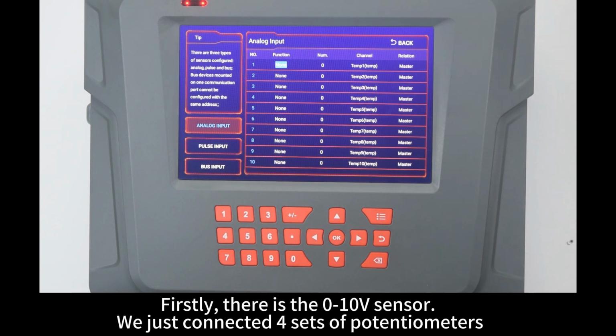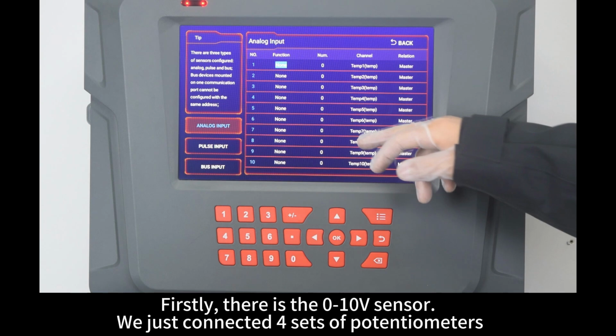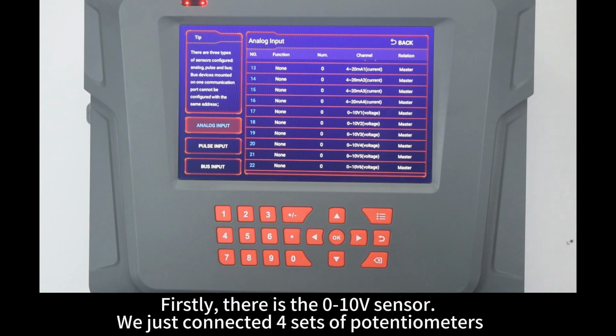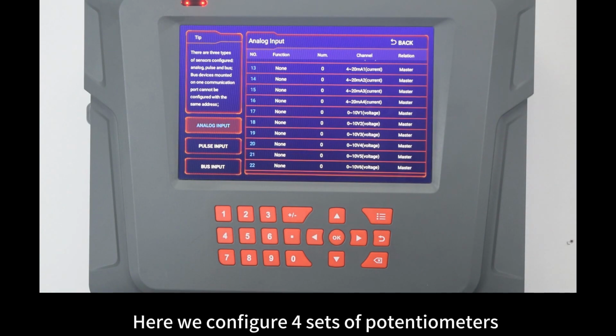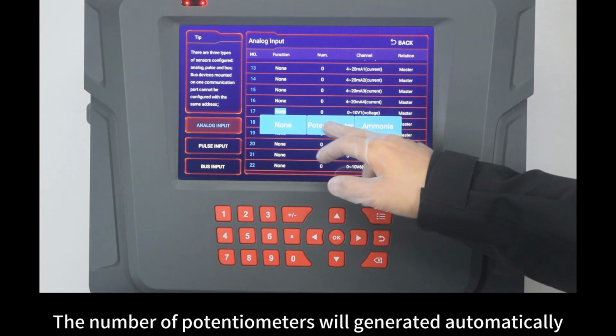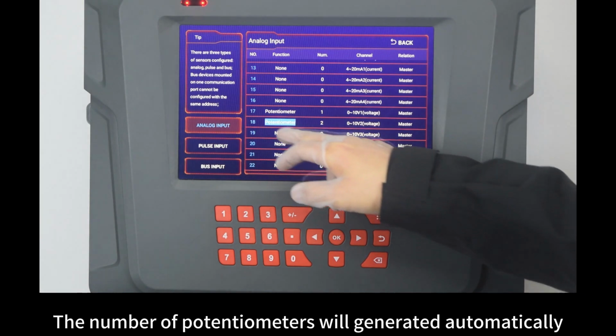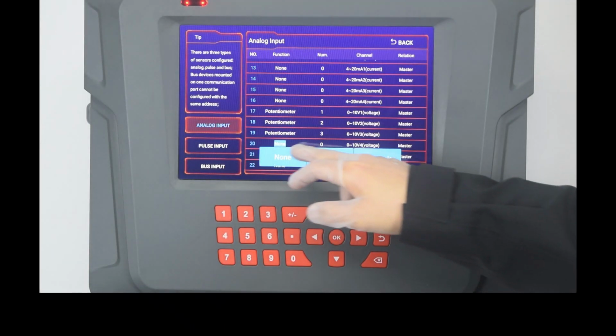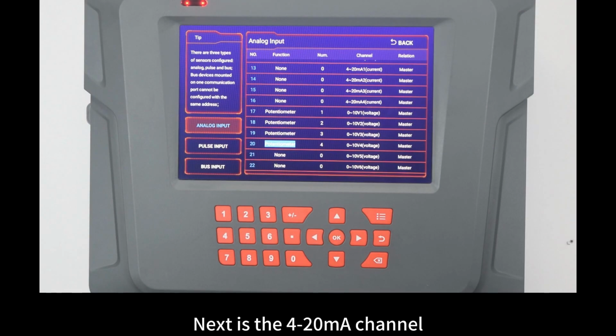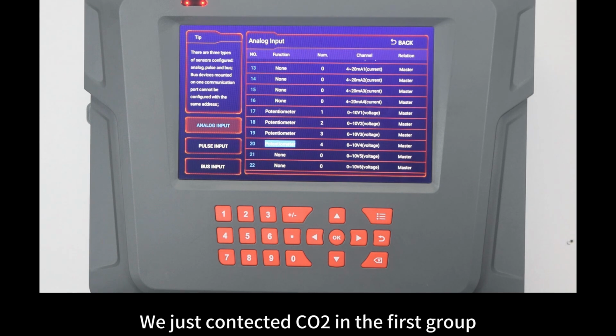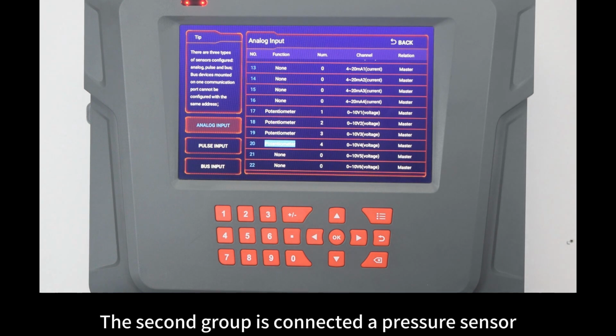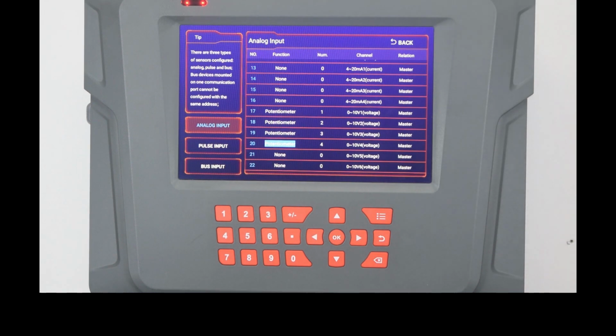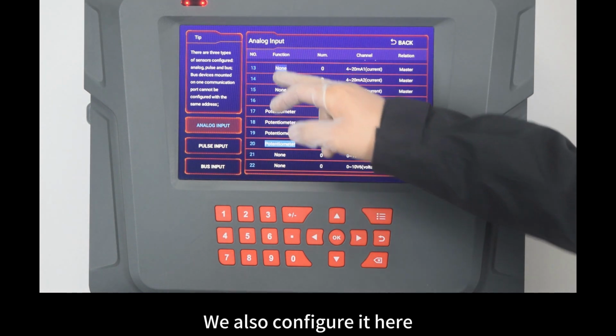Firstly, there is the 0 to 10 voltage sensor. We just connected 4 sets of potentiometers. Here we configure 4 sets of potentiometers. The number of potentiometers will generate it automatically. Next is the 4 to 20 mA channel. We just connected CO2 in the first group. The second group is connected a pressure sensor. We also configure it here.